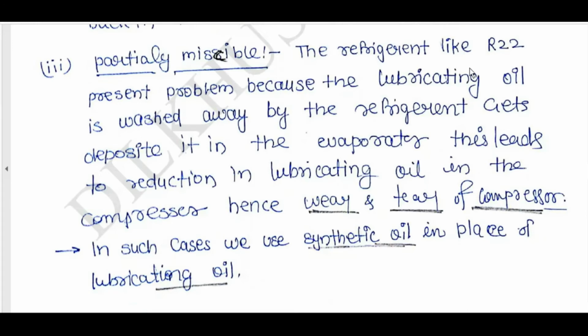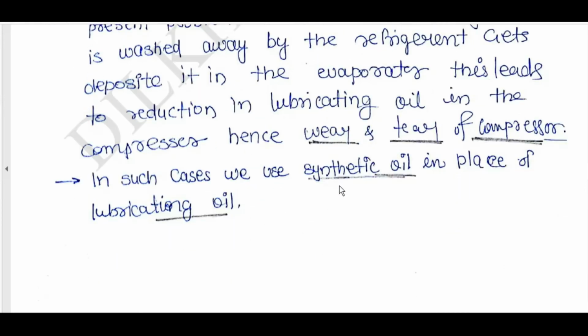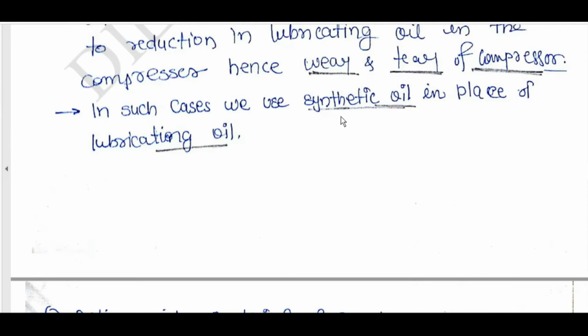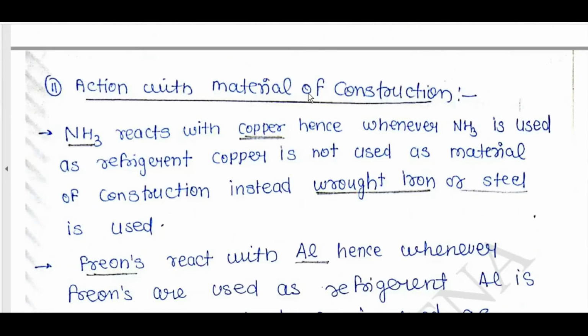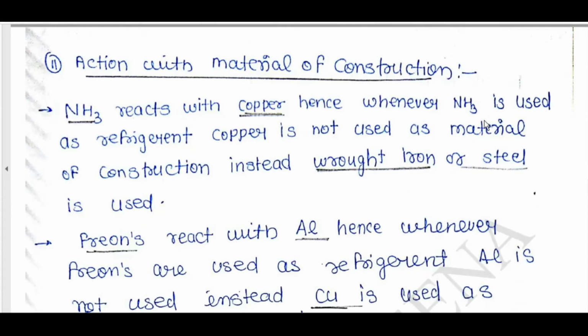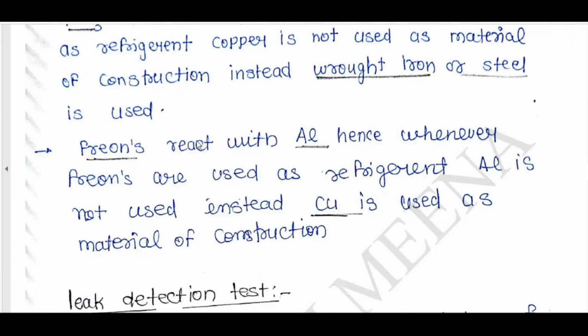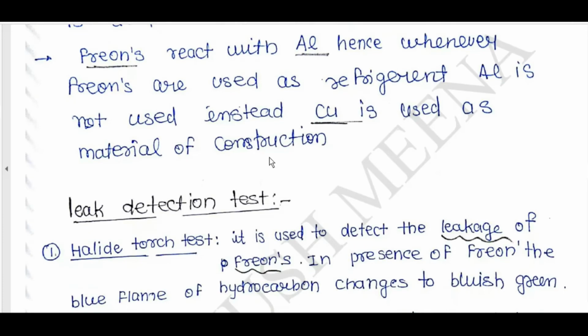Partially miscible refrigerants like R22 present a problem, because if lubricating oil is washed away by the refrigerant, it gets deposited in the evaporator. This leads to reduction of lubricating oil in the compressor, hence wear and tear of the compressor. In such cases, we use synthetic oil in place of lubricating oil. Action with material of construction. NH3 reacts with copper, hence when NH3 is used as a refrigerant, copper is not used as material of construction. Instead, wrought iron or steel is used. Freons react with aluminum, hence whenever freons are used as refrigerant, aluminum is not used. Instead, copper is used as the material of construction.